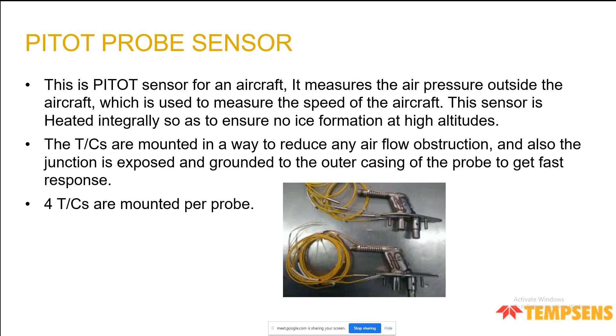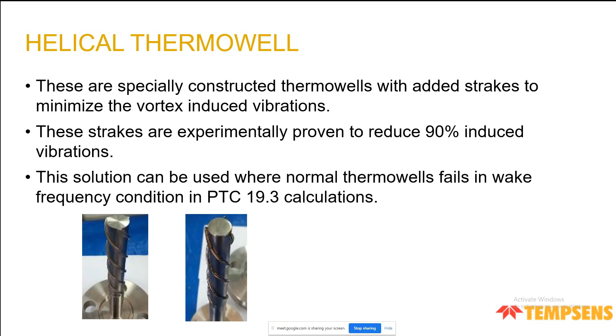This one isn't specifically for nuclear or that industry, but it's a special helical thermowell we designed for high flow rate areas. When the standard PTC 19.3 calculation for wake frequency doesn't meet requirements, vortexes can be suppressed using a helical thermowell. These can be machined with a helical profile, or we can weld helical fins onto the thermowell for better resistance against flow-induced vortexes in the pipeline.